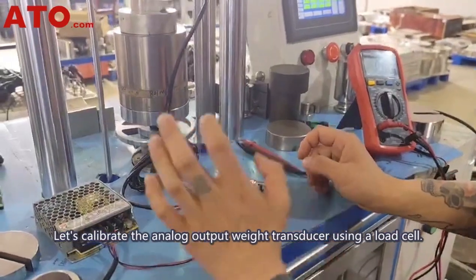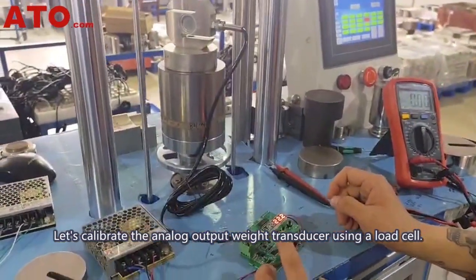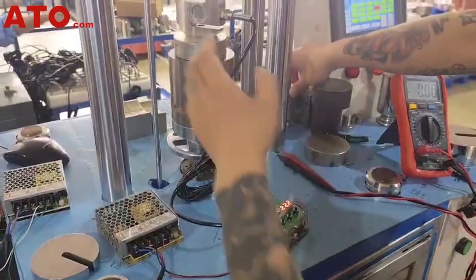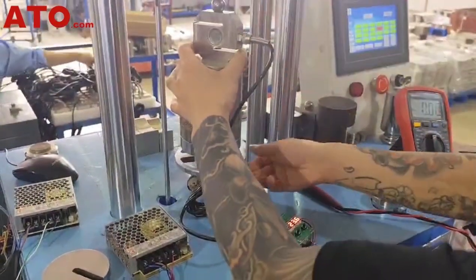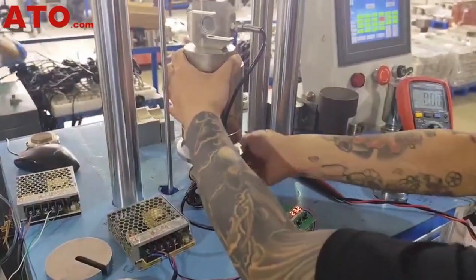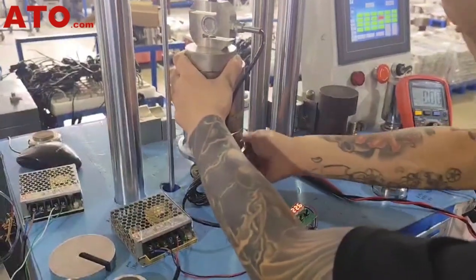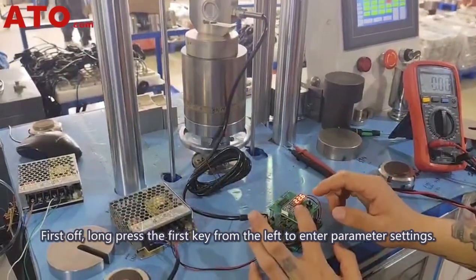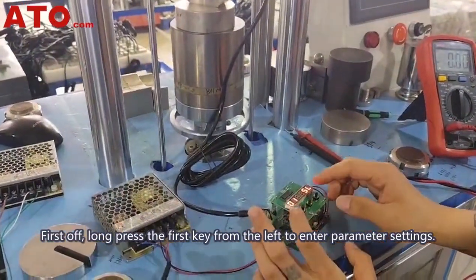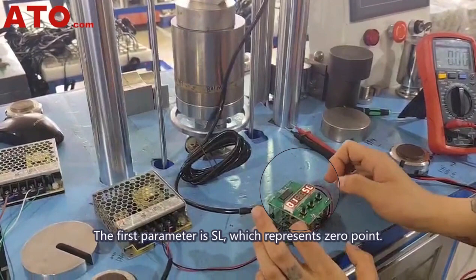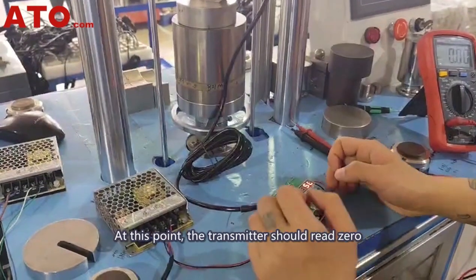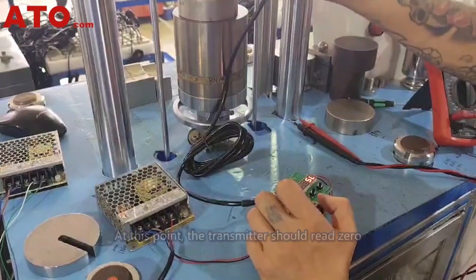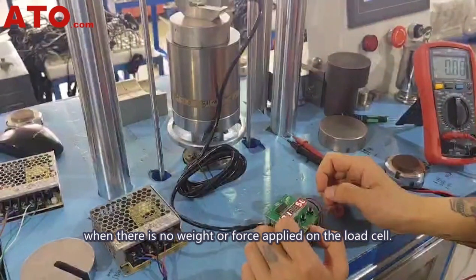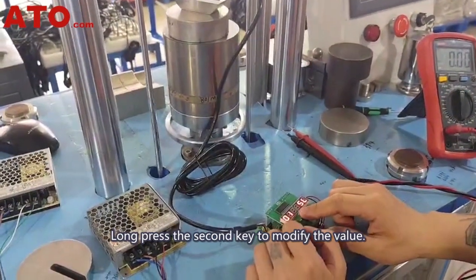Let's calibrate the analog output weight transmitter using a load cell. First off, long press the first key from the left to enter parameter settings. The first parameter is SL, which represents 0 point. At this point, the transmitter should read 0, when there is no weight or force applied to the load cell. Long press the second key to modify the value.